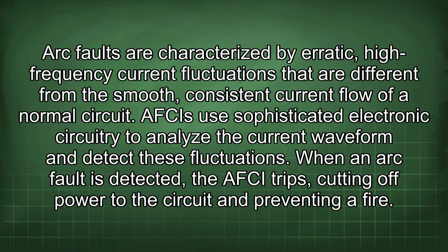Arc faults are characterized by erratic, high-frequency current fluctuations that are different from the smooth, consistent current flow of a normal circuit. AFCIs use sophisticated electronic circuitry to analyze the current waveform and detect these fluctuations. When an arc fault is detected, the AFCI trips, cutting off power to the circuit and preventing a fire.